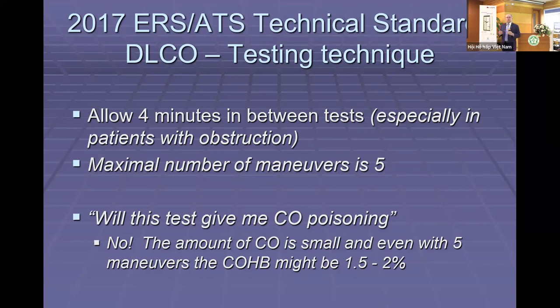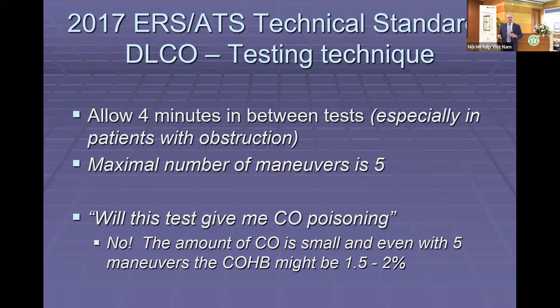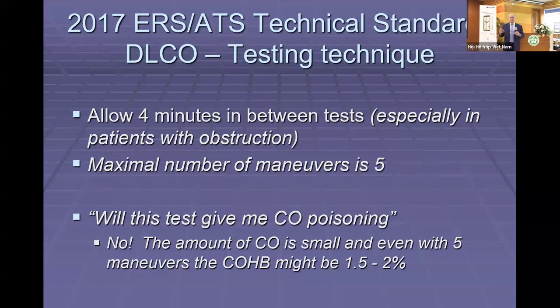The maximum number of maneuvers you can perform is set at 5. A common question is about the test gas: since there's a trace of carbon monoxide in it, will it cause CO poisoning? The answer is no. Even if you do a maximum of 5 maneuvers, your carboxyhemoglobin might go up by only about 2%.